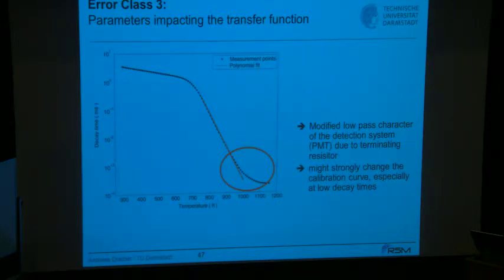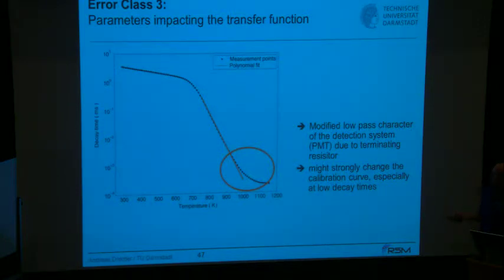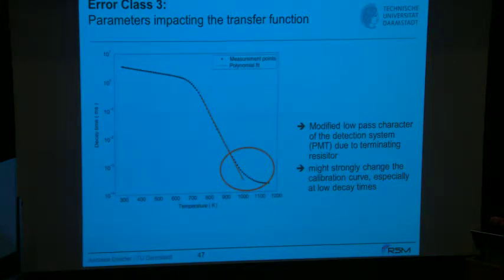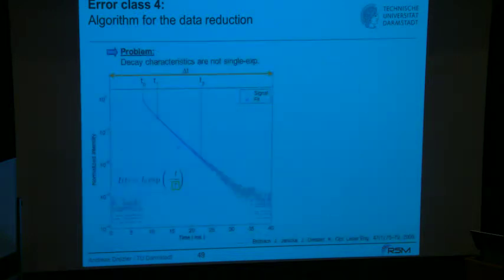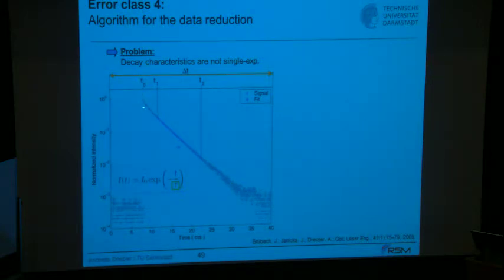Returning to the photomultiplier tube: if you choose 500-ohm rather than 50-ohm termination for higher signals, you end up with a limited minimum resolvable decay time — the signal levels out. This termination must not be changed between calibration and measurement. Regarding the algorithm, the decay is not mono-exponential everywhere: at the beginning it is certainly multi-exponential, and at later times the signal flattens due to the terminating resistor. You want to select a time range where your mono-exponential model function is reasonably justified.